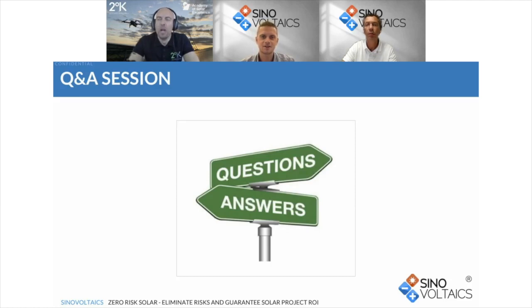What we're trying to do is balance having a representative sample without, for example, taking apart five different pallets just to get individual modules from the middle of them — that would be an extreme case, and you'd have to unpack and repack each pallet you disturb. So we try to minimize that: we unpack it, make sure it's suitably supported, test five modules straight from that pack in a vertical position, and replace them as they were removed. So they're vertically packed — we don't take the whole pack aside.